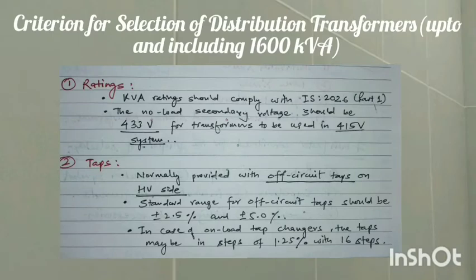Let's see the criteria for the selection of distribution transformers. First, ratings. IS Standard 2026 defines the kVA rating which should be applied for the distribution transformer, so that rating should be followed. The no-load secondary voltage should be 433 volts for transformers to be used in a 415-volt system.